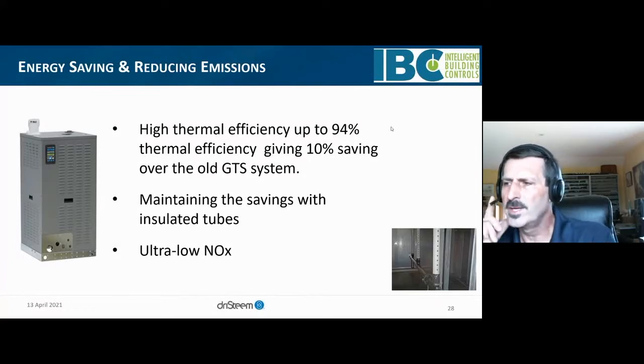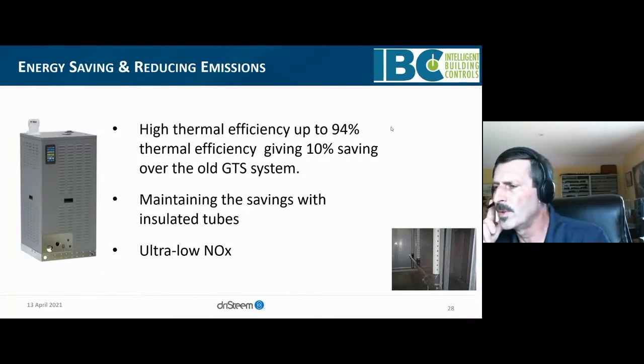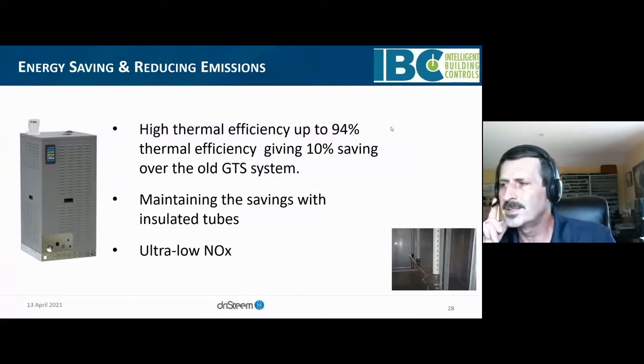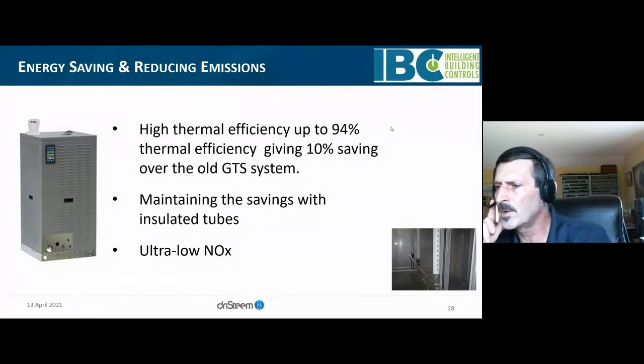We saw some other energy savings from their project by just upgrading to the more thermally efficient units. We know we were giving them at least a 10% energy savings over the older GTS systems. They're maintaining their systems with the insulated tubes on the rapid sorbs, and with the new LX, they were able to lower their carbon emissions with the new ultra-low NOx product. The existing dispersion tubes were already high efficiency.